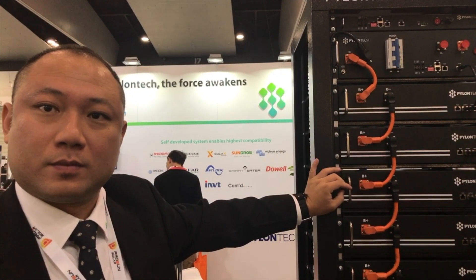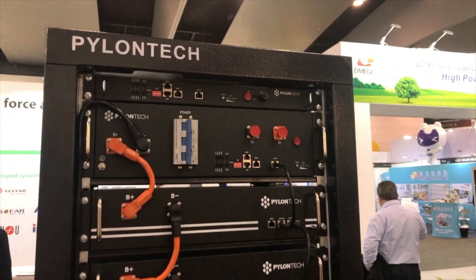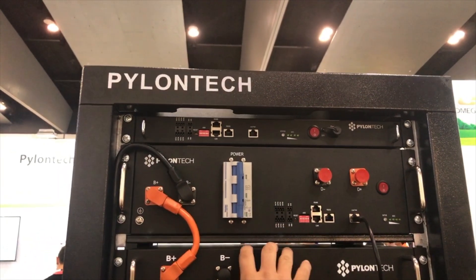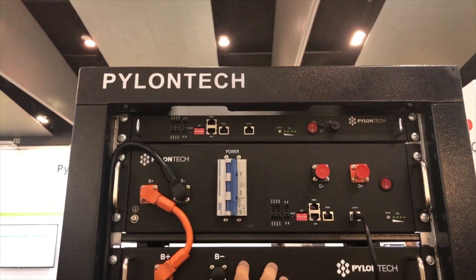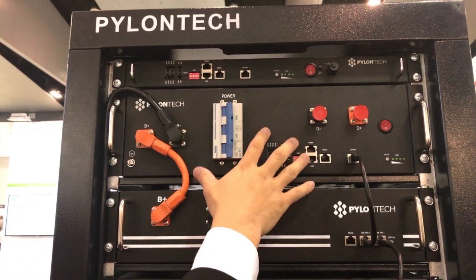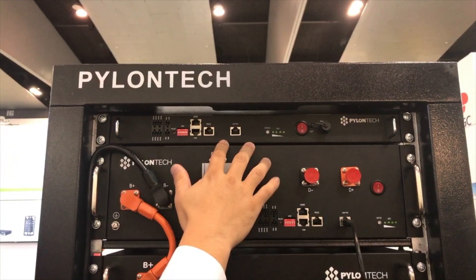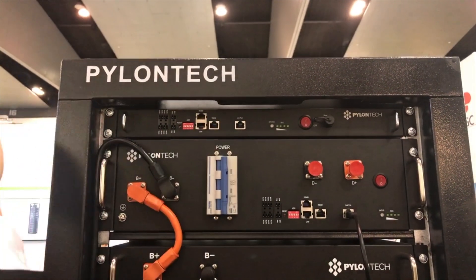You can series them to the voltage you require and they have a control unit at the top — a master BMS. Inside each module we have the BMS for protection, we call it BMU. Then here is the BMS, the second level with the main protection and communication. The third level here is the highest, going with the IP, and you need this for paralleling all the racks — normally in a big container.